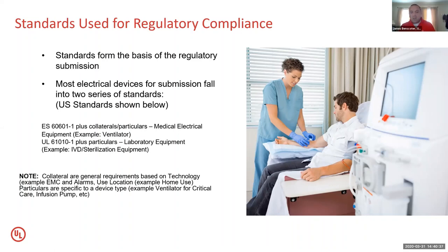Additionally, it'll have other standards that'll come into play also, such as alarm requirements, looking for electromagnetic compatibility. Now, as mentioned earlier, the amount of development and work that goes into showing compliance to all these standards can be quite large. The number of testing, number of items to go through can be quite substantial. And this is where discussion with the FDA to understand what those standards are and what you can accomplish, depending on the time frame, would need to be discussed individually on the device to determine whether full compliance, full testing compliance, or some derivative in between is necessary to address all of the relevant requirements.